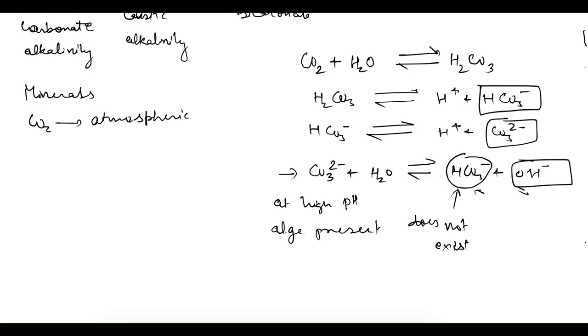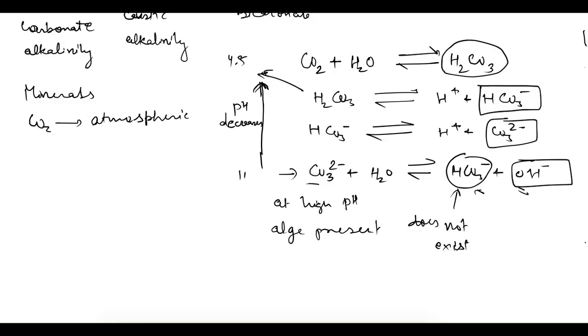All these reactions take place in a specific order with respect to pH. The last reaction (caustic alkalinity) occurs at a maximum pH of around 10 to 11 and above. As we go upward in the reaction sequence, pH decreases. The bicarbonate alkalinity is consumed at a pH of 4.5, and if pH is further decreased, the species converts into carbonic acid.